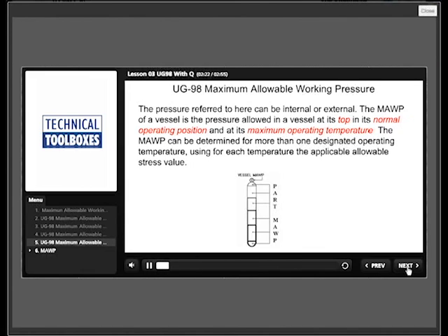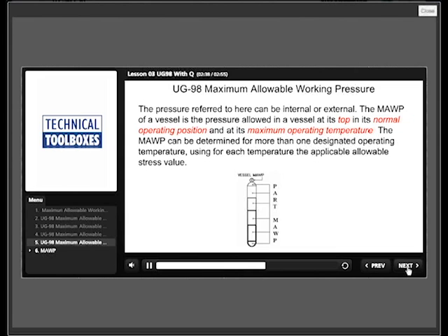The pressure referred to here can be internal or external. The MAWP of a vessel is the pressure allowed in a vessel at its top, in its normal operating position, and at its maximum operating temperature. The MAWP can be determined for more than one designated operating temperature, using for each temperature the applicable allowable stress value.